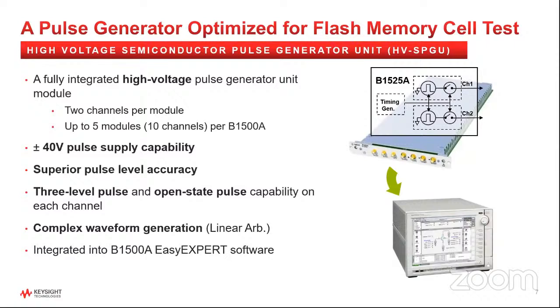Here I'm showing you our solution for flash memory cell test. We have a specialized module, the high voltage semiconductor pulse generator unit, or HV-SPGU module, designed for this type of thing. It has 2 channels per module, and you can put up to 5 modules, or 10 channels, in an instrument. The important thing is it has a plus or minus 40 volt pulse supply capability. It's got very good voltage control in its pulsing. It can do 3-level pulses as well as open state pulses on each channel. It can also generate complex waveforms, has a linear arbitrary waveform generation capability, and it's fully integrated into the software for the B1500A.